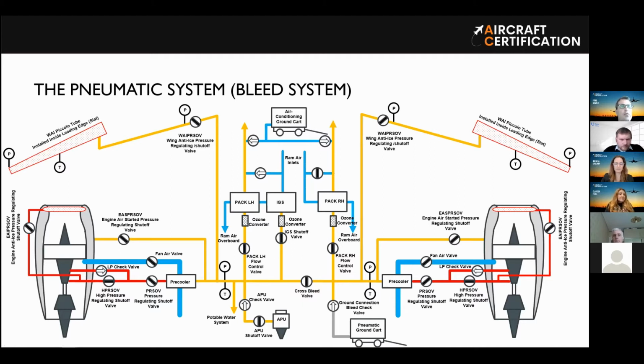This pressure regulating valve can be controlled by a digital controller that will read the pressure in the manifold and control the set points. And inside the fire zone, you have a pre-cooler to reduce the temperature of the bleed by using the bypass flow of the engine. So here you have the fan valve. The fan valve is a modulating valve that has its modulation controlled by the temperature of the bleed.